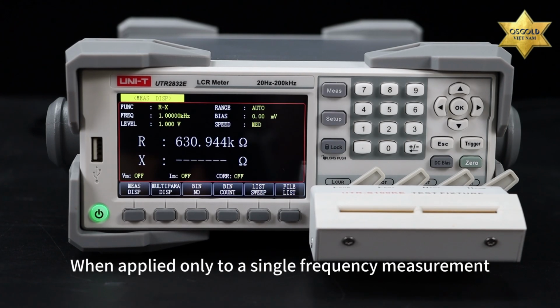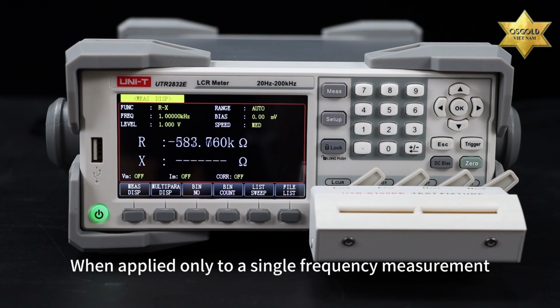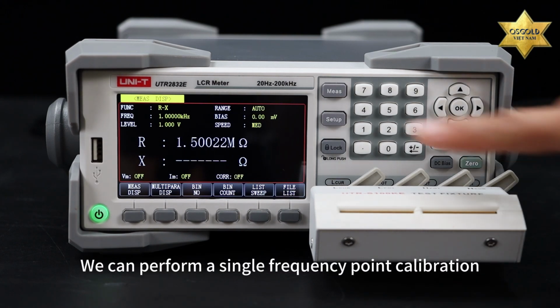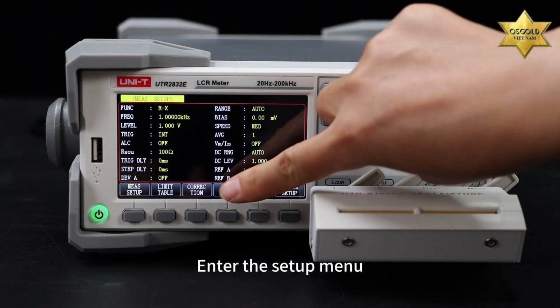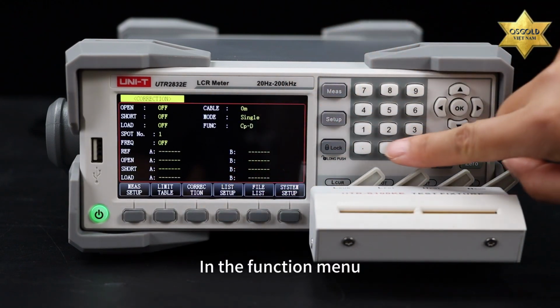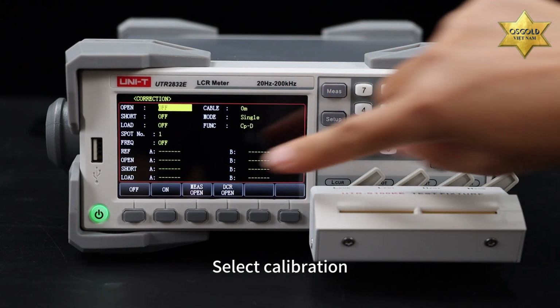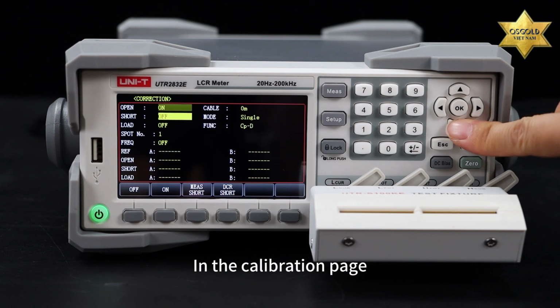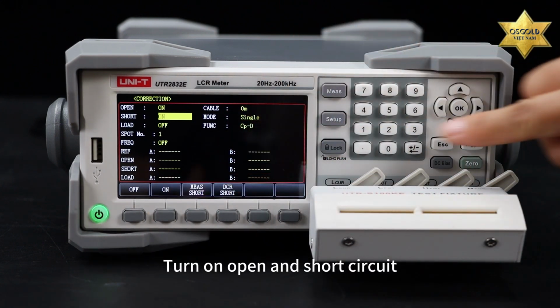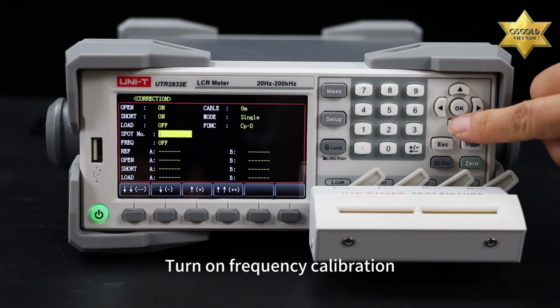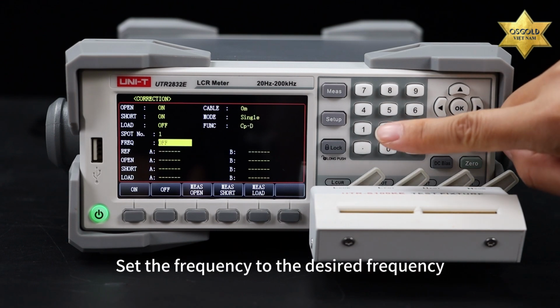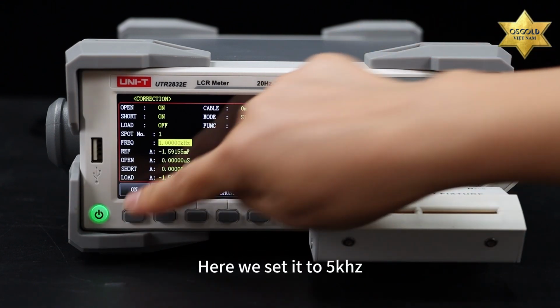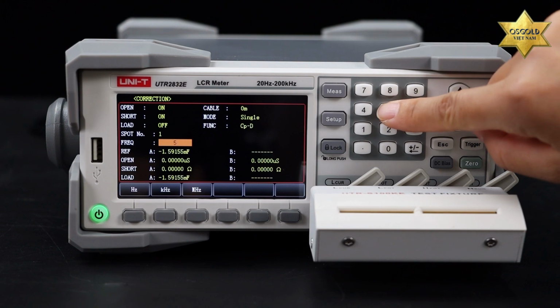When applied only to a single frequency measurement, we can perform a single frequency point calibration. Enter the Setup menu. In the Function menu, select Calibration. In the Calibration page, turn on Open and Short Circuit. Turn on Frequency Calibration. Set the frequency to the desired frequency. Here we set it to 5 kHz.